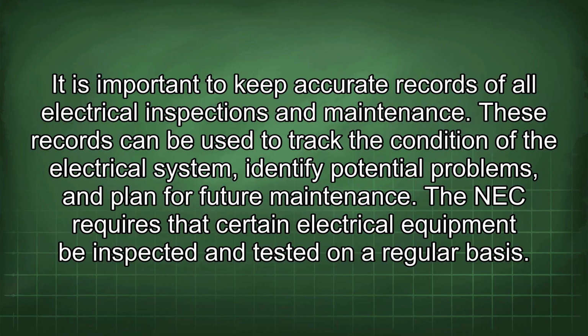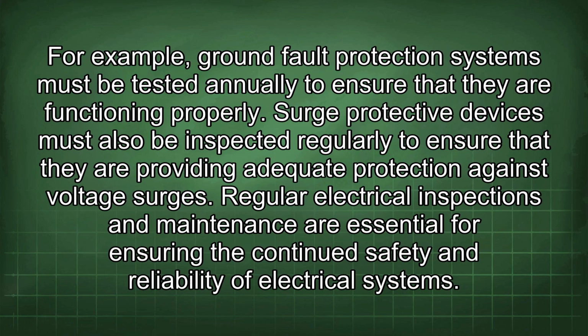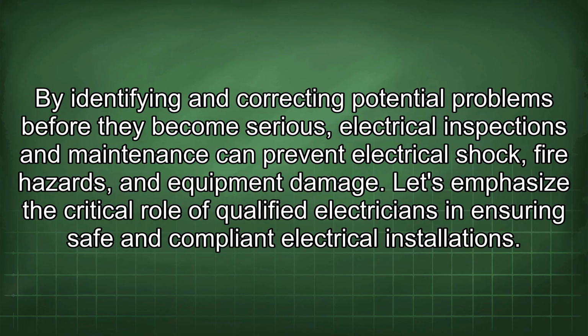These records can be used to track the condition of the electrical system, identify potential problems, and plan for future maintenance. The NEC requires that certain electrical equipment be inspected and tested on a regular basis. For example, ground fault protection systems must be tested annually to ensure that they are functioning properly. Surge protective devices must also be inspected regularly to ensure that they are providing adequate protection against voltage surges. Regular electrical inspections and maintenance are essential for ensuring the continued safety and reliability of electrical systems. By identifying and correcting potential problems before they become serious, electrical inspections and maintenance can prevent electrical shock, fire hazards, and equipment damage.